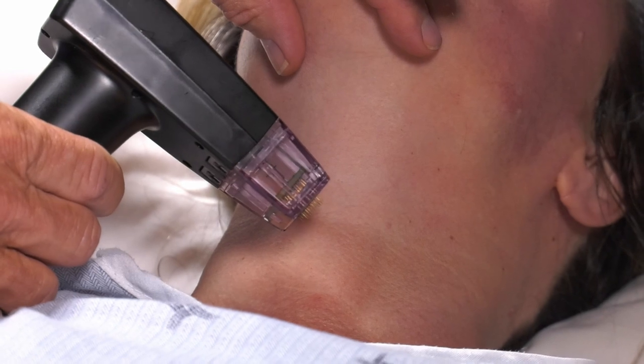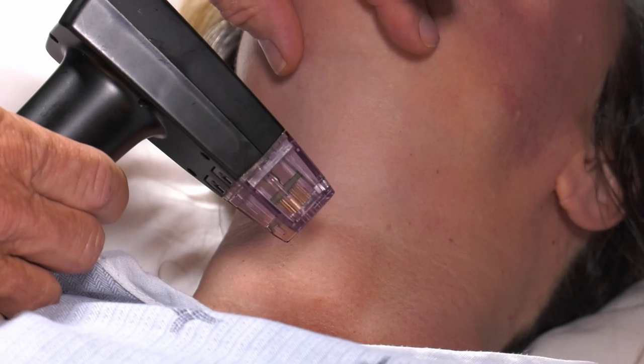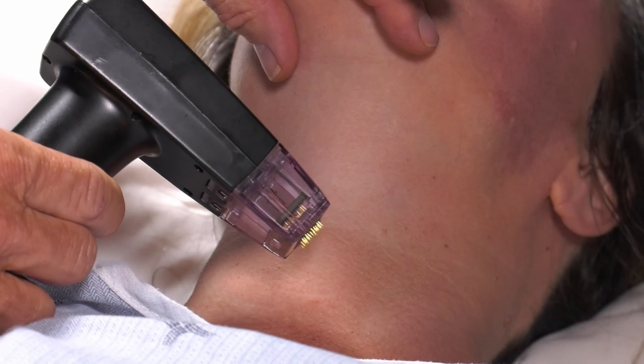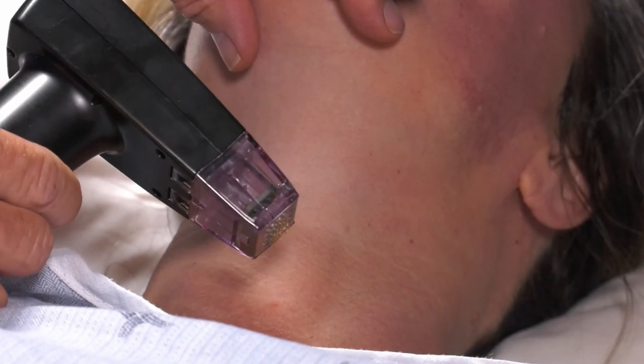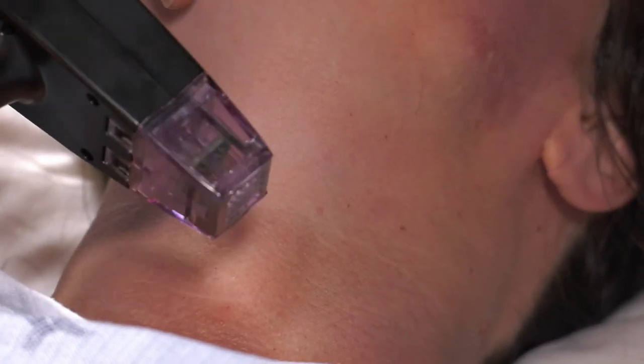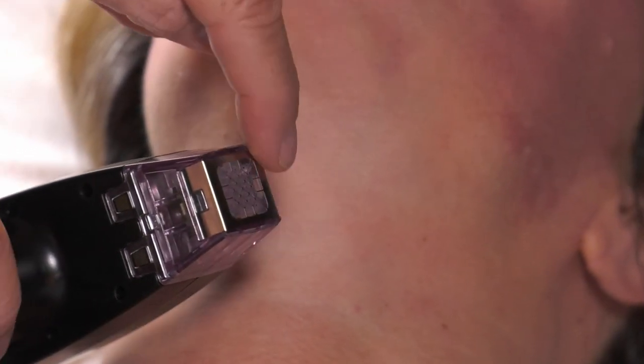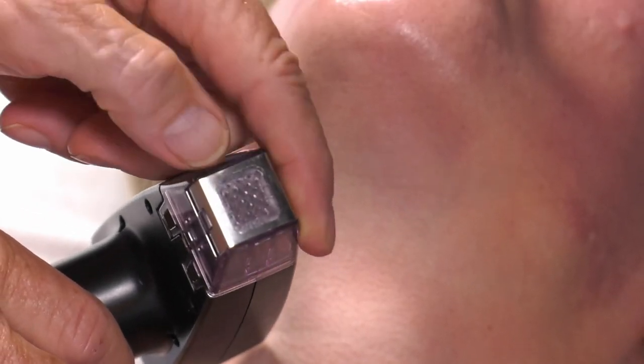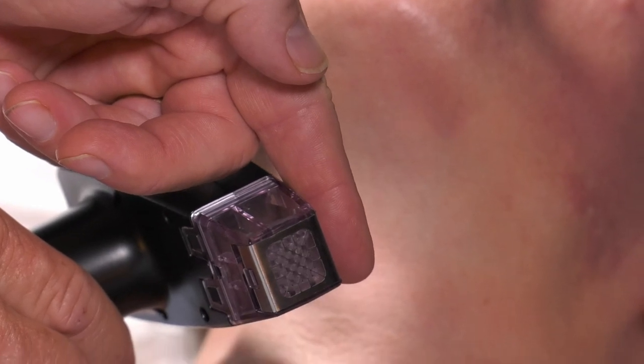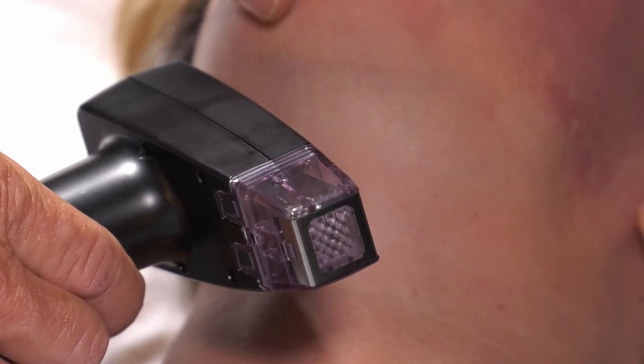Every time this pulses, it's going to pulse when it's fully extended. Those are gold-plated needles — only the tip, 800 microns, is uncoated. Each one of the tips is positive and monopolar, which differentiates it from microneedling, plus they have way more energy. The RF flows up to the negative electrodes. The side electrodes are negative, and actually the triangles in the middle where the pins come out are also negatively charged. So the papillary and reticular dermis treatment is non-ablative, and the coagulation occurs at the adipocyte level.